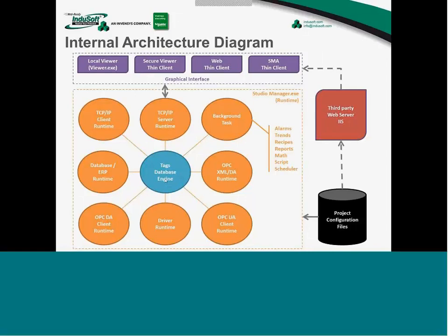They do not provide any graphical interface. So the graphical interface is an independent process, and it communicates with the Studio Manager through the TCP/IP server runtime task from Studio Manager. So this link here between the graphical interface and Studio Manager is over TCP/IP, which gives us a lot of flexibility to run the graphical interface on the same computer where Studio Manager is running, where the runtime is running, or in a remote computer. And then it is what we call a thin client solution.